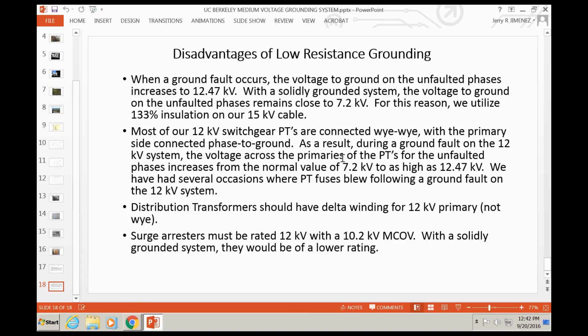And I started thinking about this, and I thought, well, this makes sense. Normally, these potential transformers are connected Y to Y, and of course, on the 12 kV system, we don't carry our neutral. So they get connected basically from phase to ground, ground being the ground bus of the switchgear. So during normal operating conditions, the voltage across each PT is 7.2 kV. However, when we get a ground fault, the voltage on the primary of the PTs for the unfaulted phases increases to 12.47 kV. And the PTs will handle that for a little bit of time, and the fuses will as well, but for probably much more than a few tenths of a second, the fuses are just going to blow. So we've had several occasions where PT fuses blew following a ground fault on the 12 kV system. It's just something we have to keep in mind.